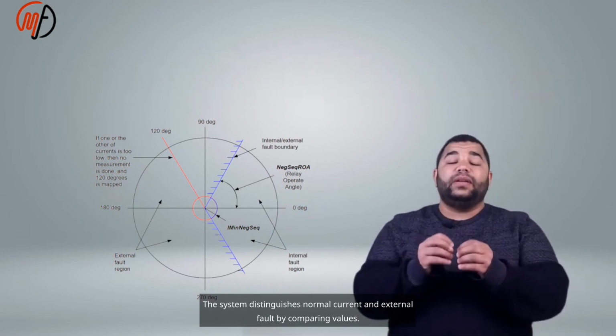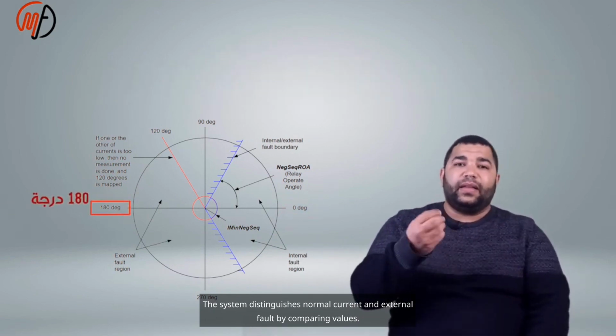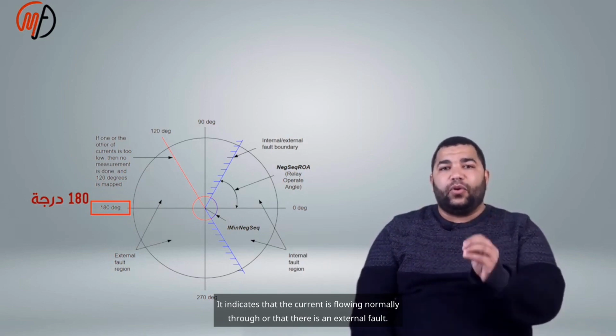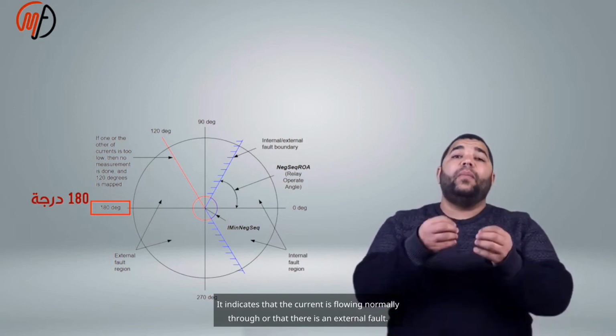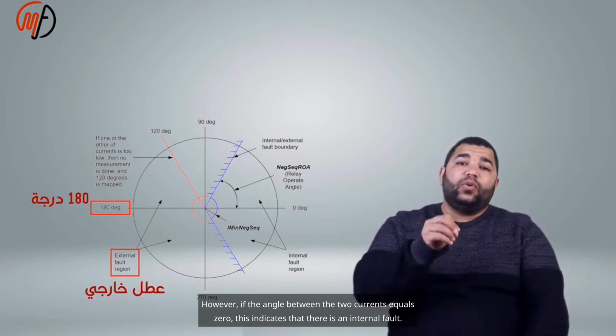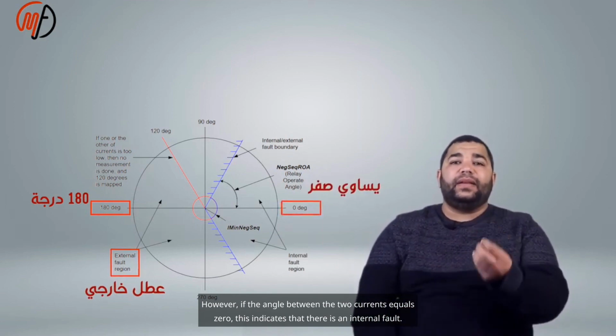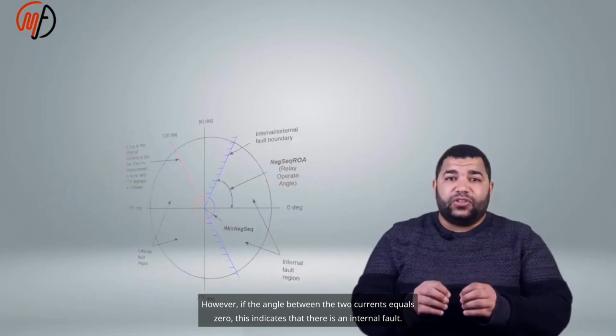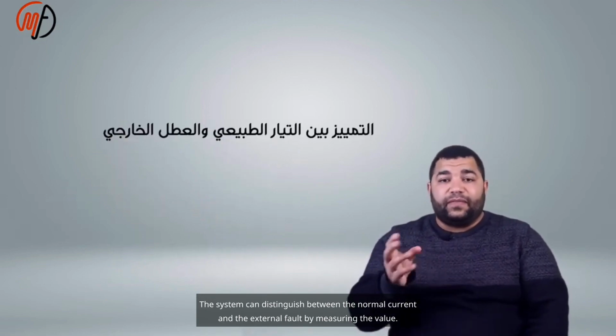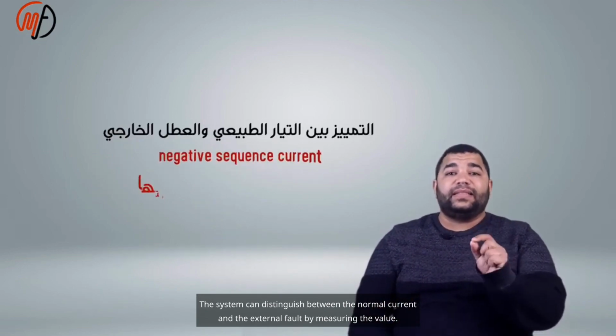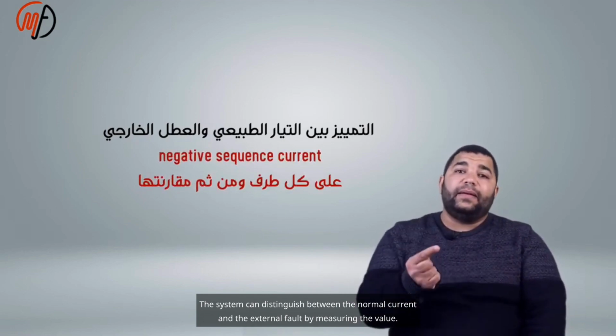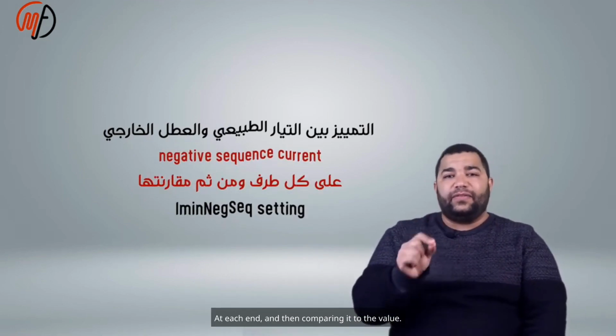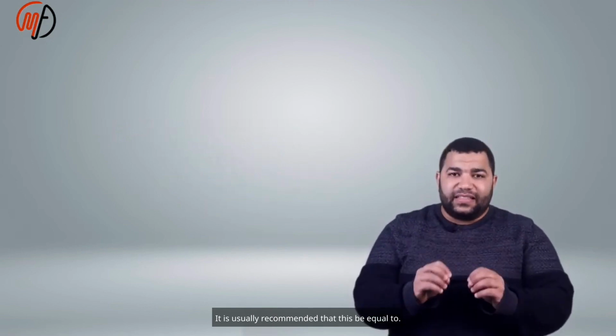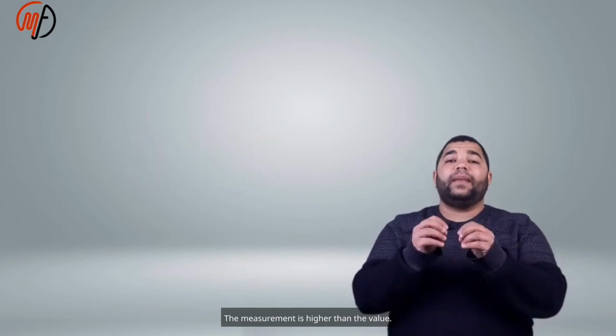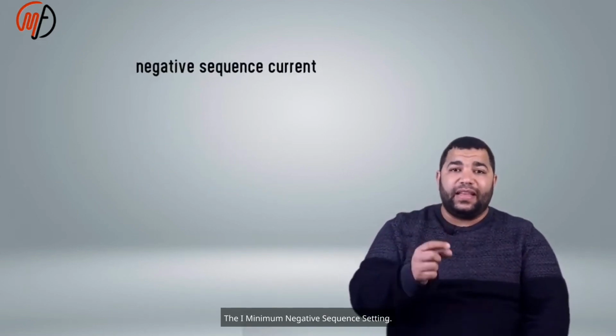The system distinguishes normal current and external fault by comparing values. It indicates that the current is flowing normally through, or that there is an external fault. However, if the angle between the two currents equals 0, this indicates that there is an internal fault. The system can distinguish between the normal current and the external fault by measuring the value at each end, and then comparing it to the setting value. It is usually recommended that this be equal to the setting, where the measurement is higher than the I minimum negative sequence setting.